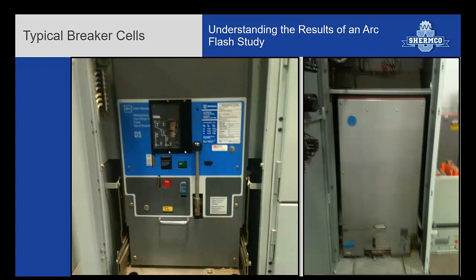These are airframe breakers. That's a 480 volt DS breaker on the left and a medium voltage ITE breaker on the right. These are airframe, so every time they open under any kind of load, because they're breaking the arc in air and they have arc chutes, you'll see the flash does still happen in the cubicle, even though it's in the breaker. So with airframe you have to be kind of careful. You can see the flash under just normal operation, under normal faults.